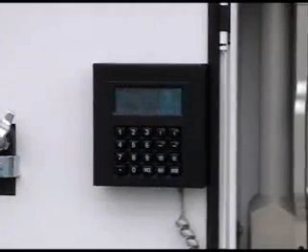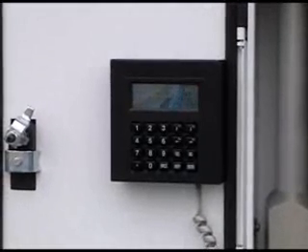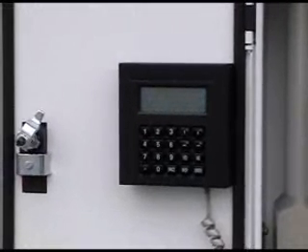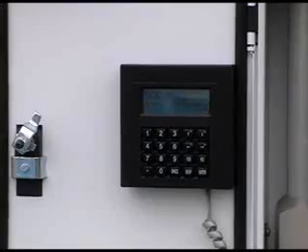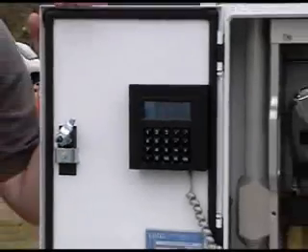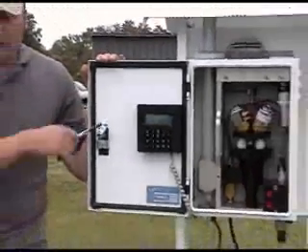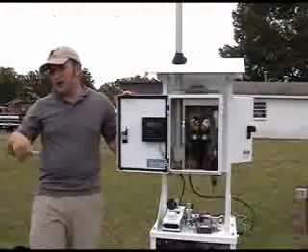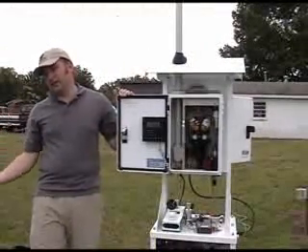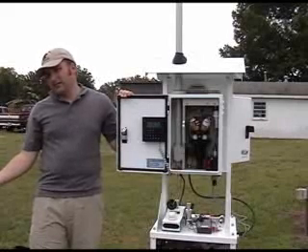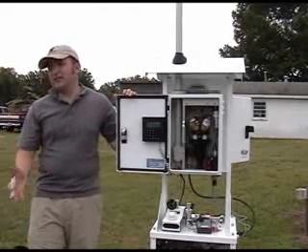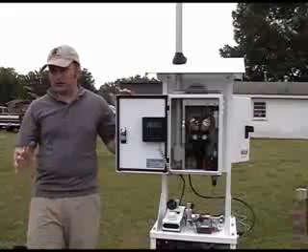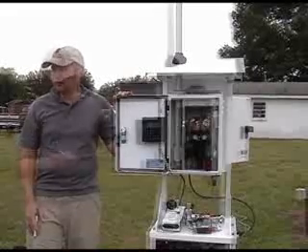Because if that 48 hours is really strict, what you can do with the sampler is, say tomorrow is the run day. You come here to do your filter change. It's ready to run tomorrow. With alternate sample day, it'll say tomorrow, and you can change it for Monday. So you basically skip Friday, you get Monday, and are able to pick it up within the 48-hour window. That's just an example of how you can make use of alternate sample day if you want to adhere strictly to that 48 hour. We step through that.